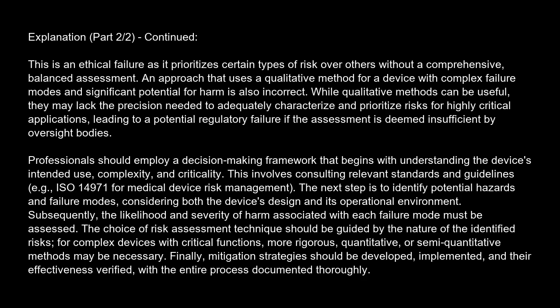The next step is to identify potential hazards and failure modes, considering both the device's design and its operational environment. Subsequently, the likelihood and severity of harm associated with each failure mode must be assessed. The choice of risk assessment technique should be guided by the nature of the identified risks. For complex devices with critical functions, more rigorous, quantitative, or semi-quantitative methods may be necessary. Finally, mitigation strategies should be developed, implemented, and their effectiveness verified, with the entire process documented thoroughly.